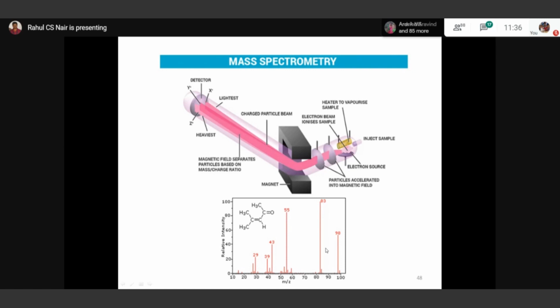There are two types here: matrix-assisted laser desorption ionization, or MALDI, mass spectrometry, and the electrospray ionization technique. Both are available in our institute. In the first case, a laser is used, so the sample has to be prepared with suitable processing techniques to make it sensitive to laser desorption. The matrix is a chemical compound added to the sample in a very large ratio, for example 10,000 to one, so that the sample won't deteriorate and you can study it with the laser. In electrospray ionization, you cover the sample with a buffer molecule and heat it so that the solvent escapes, and then we analyze the ions. So the difference lies in the method used to produce ions from the molecule being analyzed.